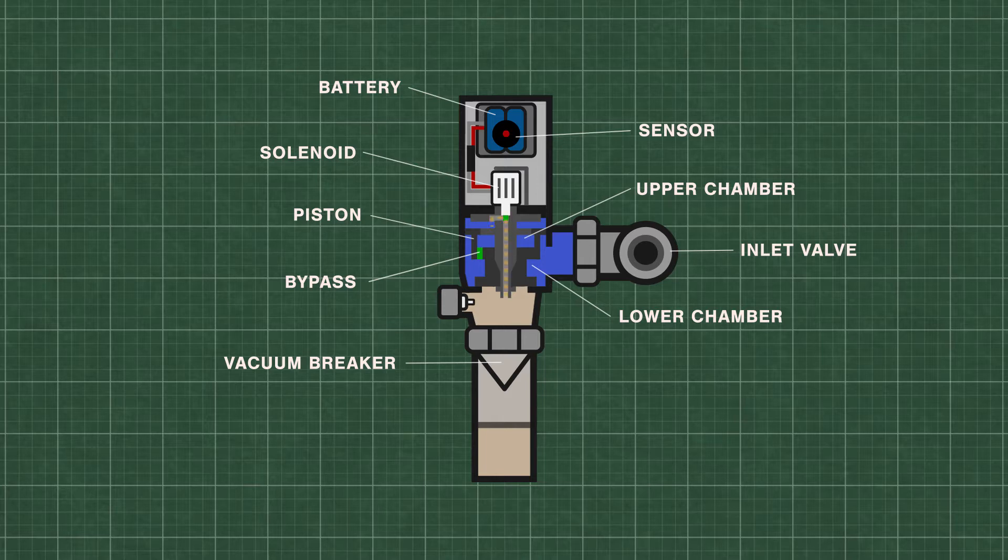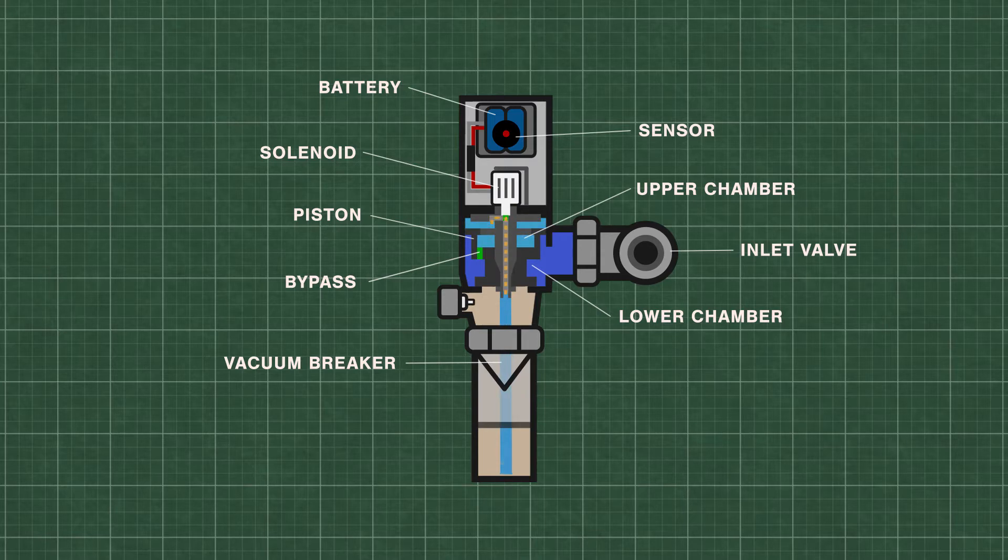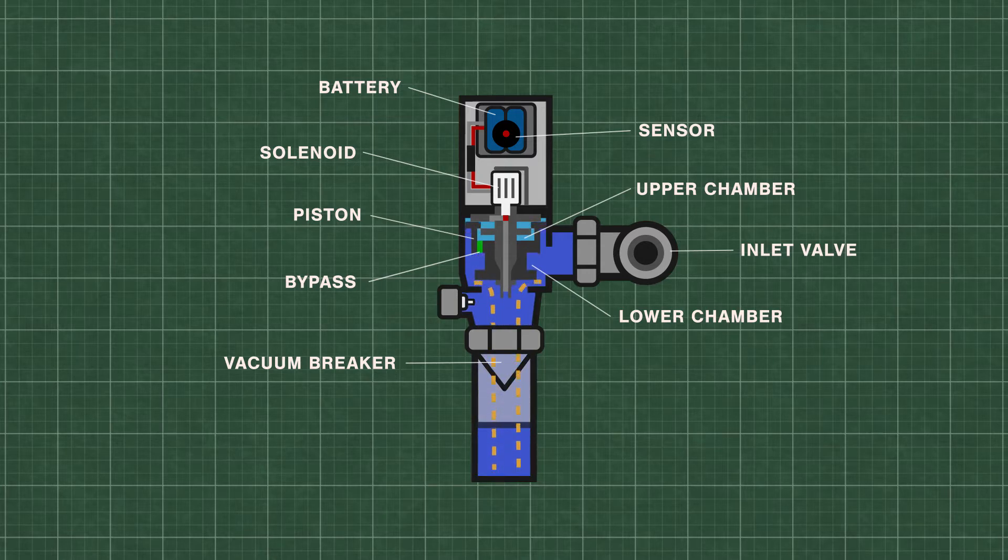When the sensor is triggered, the solenoid activates and releases water from the upper chamber which decreases the pressure. High pressure water from the inlet now lifts the piston up and travels down the flush pipe.